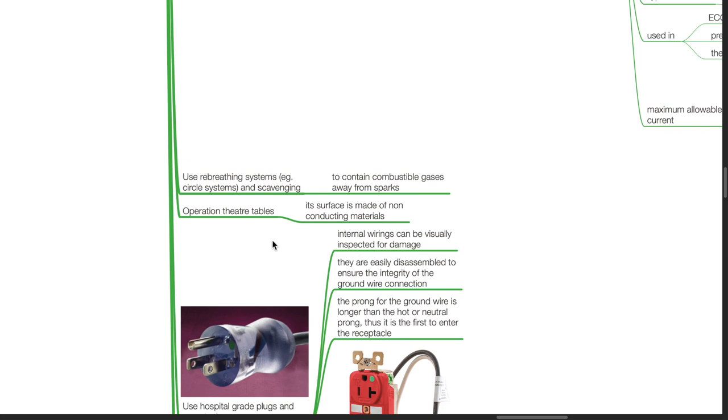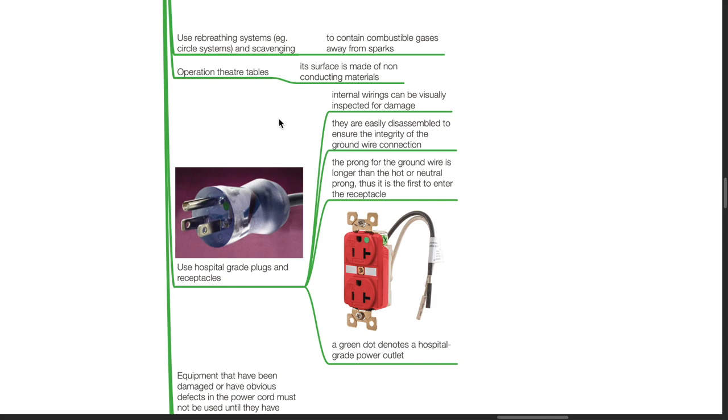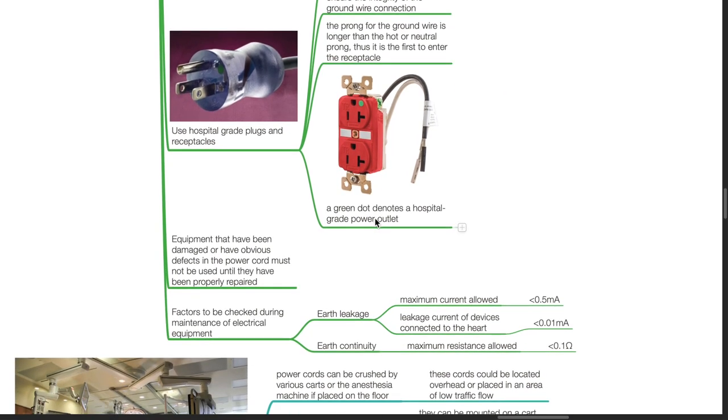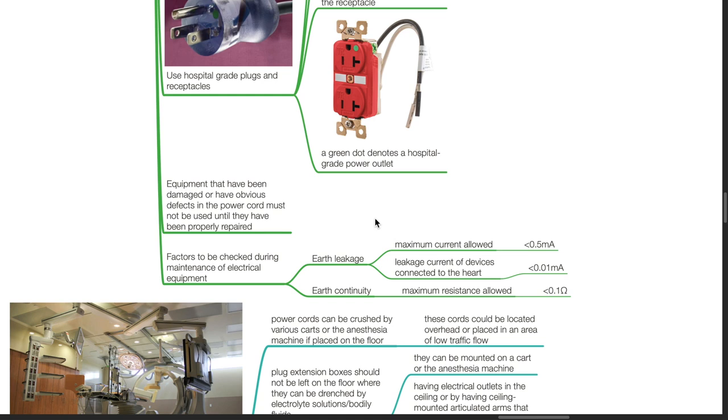We should use rebreathing systems such as circle systems and scavenging to contain combustible gases away from sparks. Operation theater tables should have non-conducting surfaces. Use hospital grade plugs and receptacles where internal wirings can be visually inspected for damage and easily disassembled to ensure integrity of ground wire connection. The prong for the ground wire is longer, so it enters the receptacle first. A green dot denotes a hospital grade power outlet. Equipment with damaged power cords must not be used until properly repaired. Factors to be checked during maintenance include earth leakage with maximum current less than 0.5 milliamps, or less than 0.01 milliamps for devices connected to the heart, and earth continuity with maximum resistance less than 0.1 ohms.